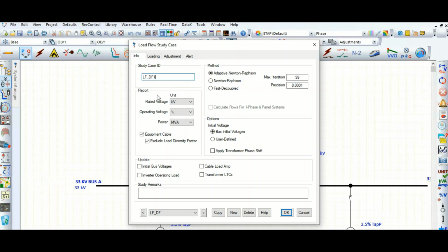Okay, here it will calculate as per the Newton-Raphson method or the adaptive Newton-Raphson method for the iteration, and the maximum iteration is 99. By default, ETAP will provide that, and the precision is 0.0001. This is the precision, so you can reduce this precision also, but the error will be more. So this is the typical value ETAP will provide. No need to change it here.